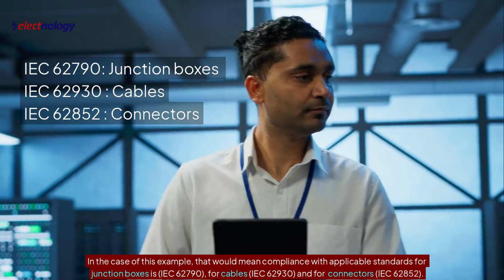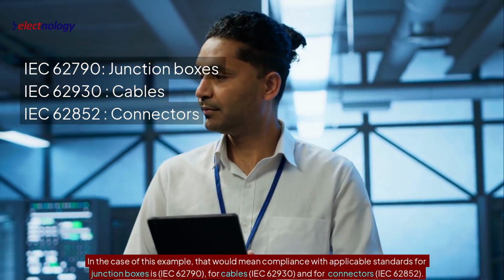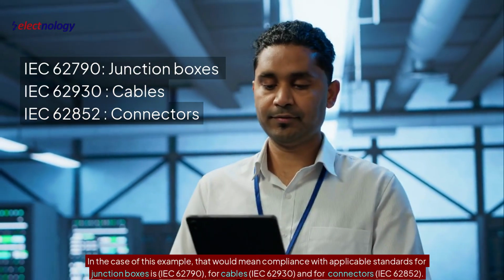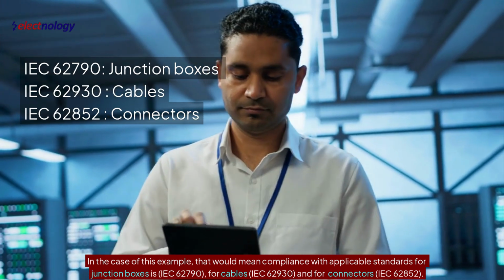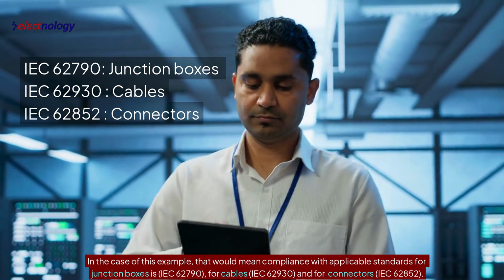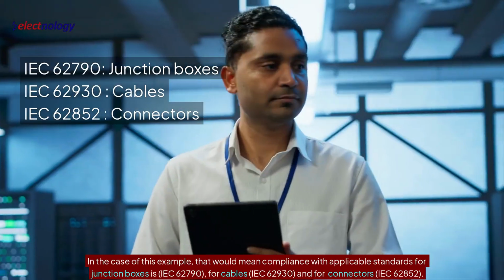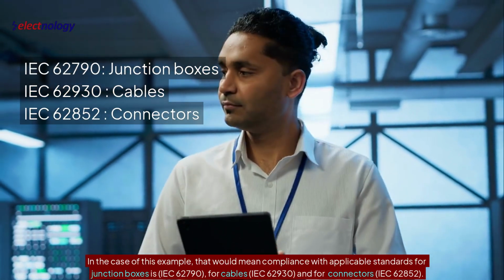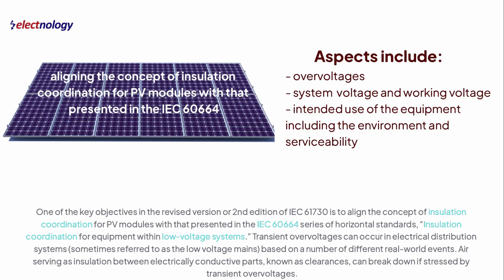In the case of this example, that would mean compliance with applicable standards: for junction boxes, IEC 62790; for cables, IEC 62930; and for connectors, IEC 62852. One of the key objectives in the revised version, or second edition, of IEC 61730 is to align the concept of insulation coordination for PV modules with that presented in the IEC 60664 series of horizontal standards, insulation coordination for equipment within low-voltage systems.